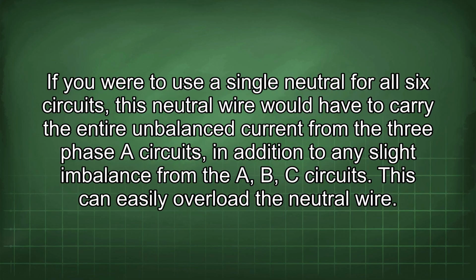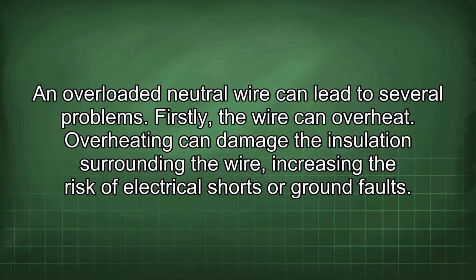If you were to use a single neutral for all 6 circuits, this neutral wire would have to carry the entire unbalanced current from the 3 phase A circuits, in addition to any slight imbalance from the A, B, C circuits. This can easily overload the neutral wire. An overloaded neutral wire can lead to several problems. Firstly, the wire can overheat. Overheating can damage the insulation surrounding the wire, increasing the risk of electrical shorts or ground faults.